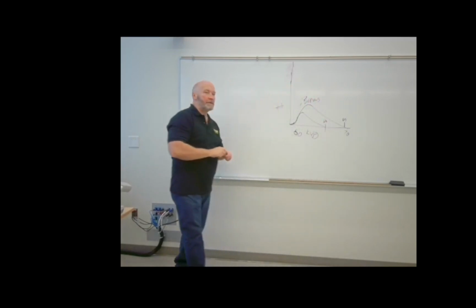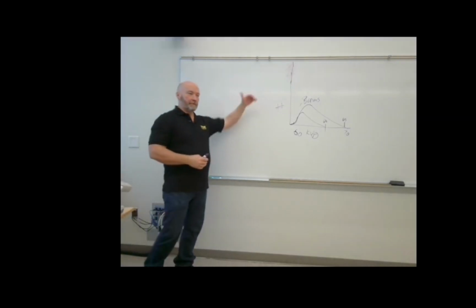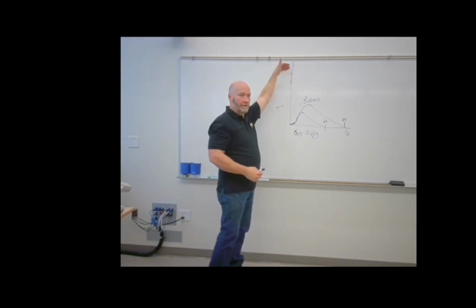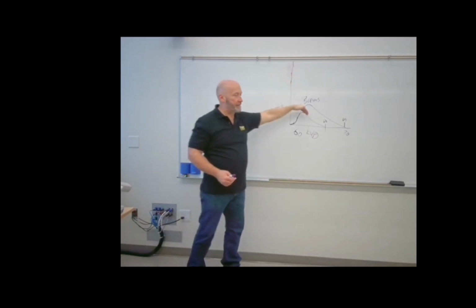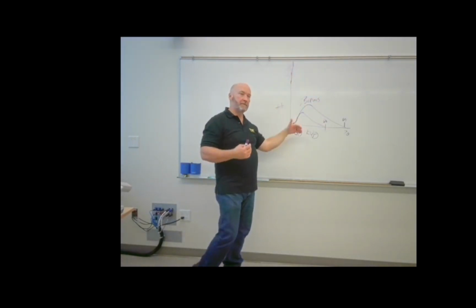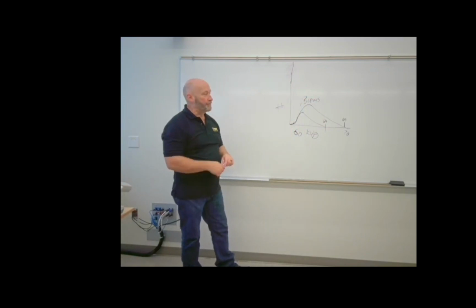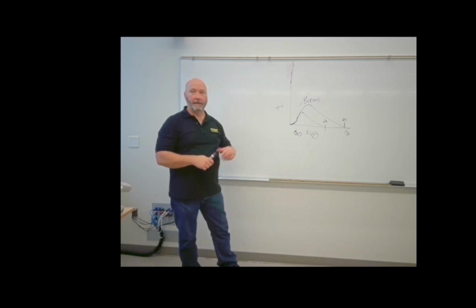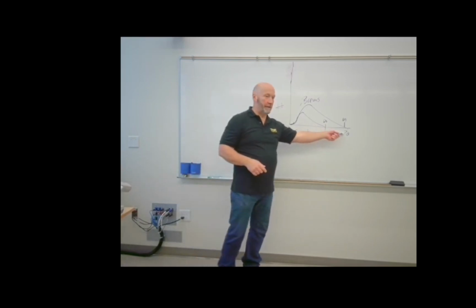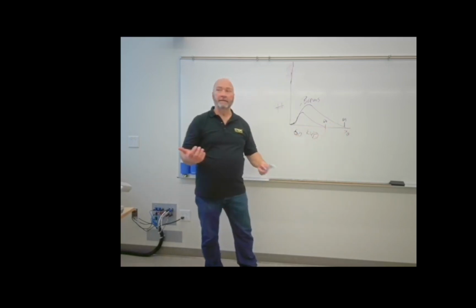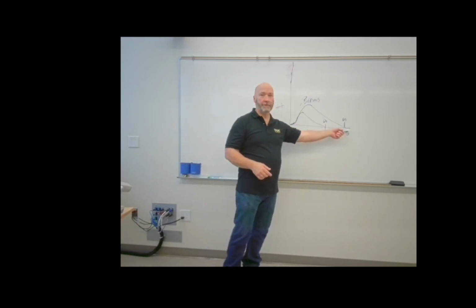All right, so this is our emission spectrum. The creation spectrum is what gave us all those low energy X-ray photons. That's at the target. This is after it comes out of the housing. This is what we expose the patient to. Much safer, but notice that in all that, the only thing that we really changed by running it through all that filtration was eliminated low energy X-ray photons. Peak energy is only controlled by kVp. All right, nothing else. But what else does kVp control? Well, we got more penetration, so we have a higher.